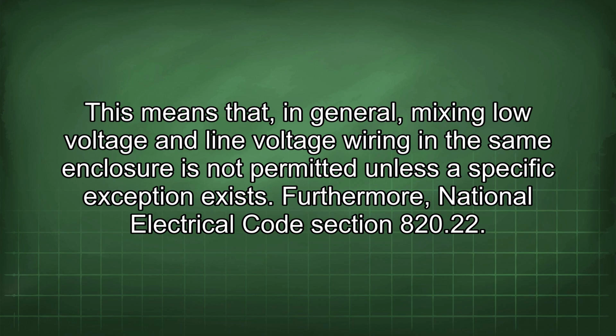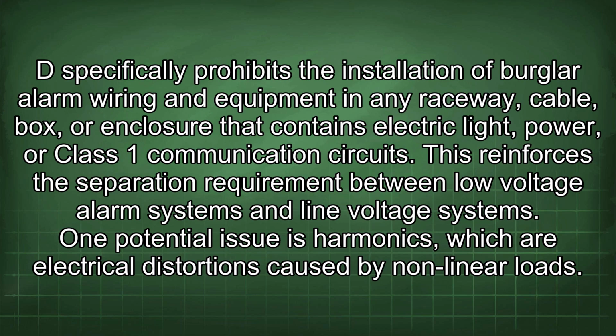a specific exception exists. Furthermore, National Electrical Code Section 820.22 specifically prohibits the installation of burglar alarm wiring and equipment in any raceway, cable, box, or enclosure that contains electric light, power, or Class 1 communications circuits. This reinforces the separation requirement between low-voltage alarm systems and line-voltage systems.